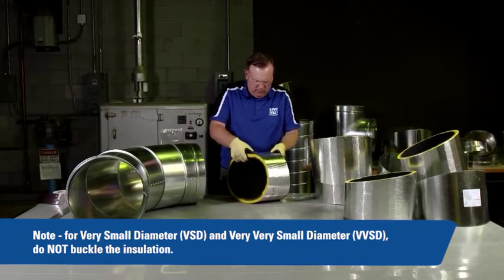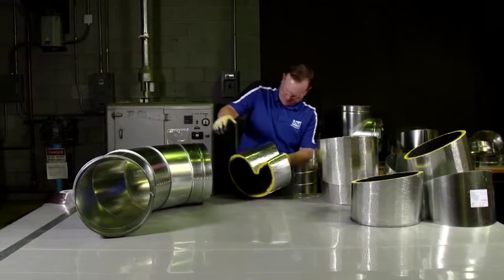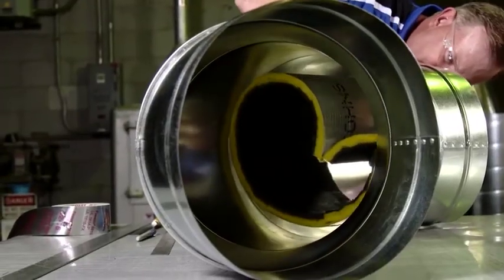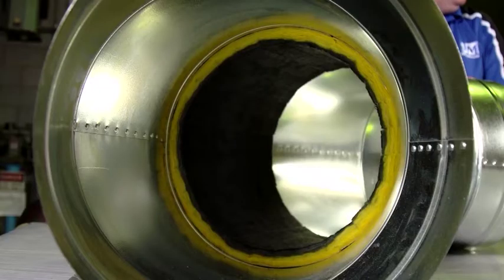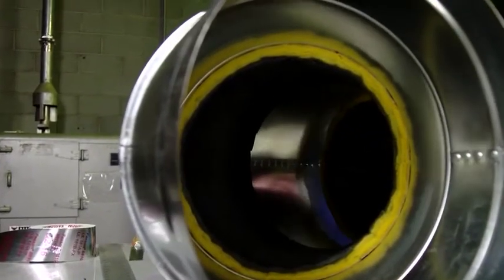Now take the piece that will fit in the middle of the duct and buckle it into a heart shape. Slide the Spiracoustic Plus into the middle of the duct, ensuring that the seam where you clamped the gore band is in line with the seam of the duct. Release the insulation and allow it to expand into place.